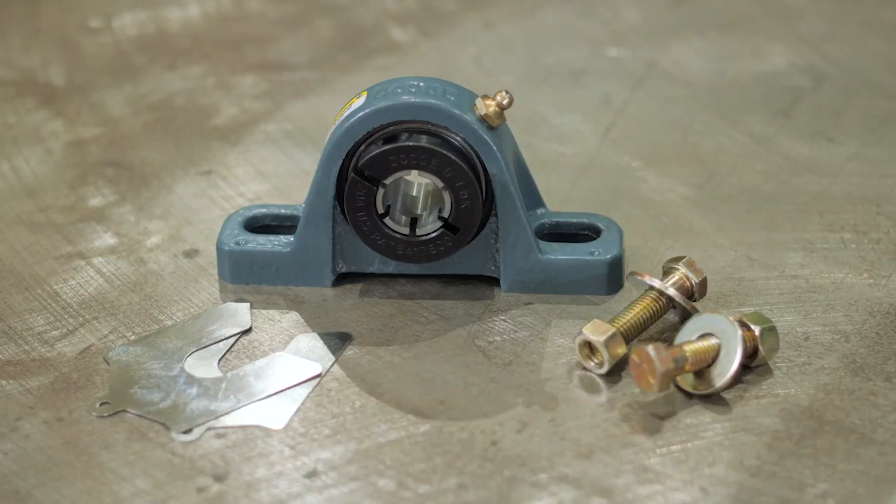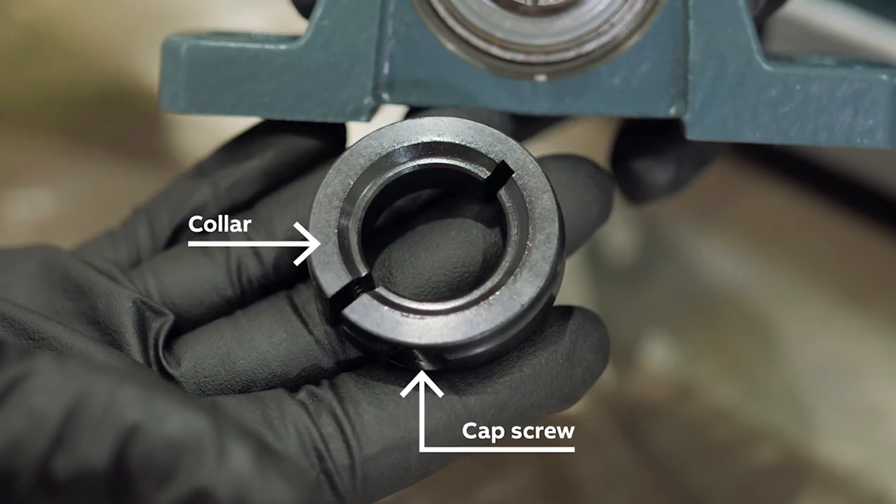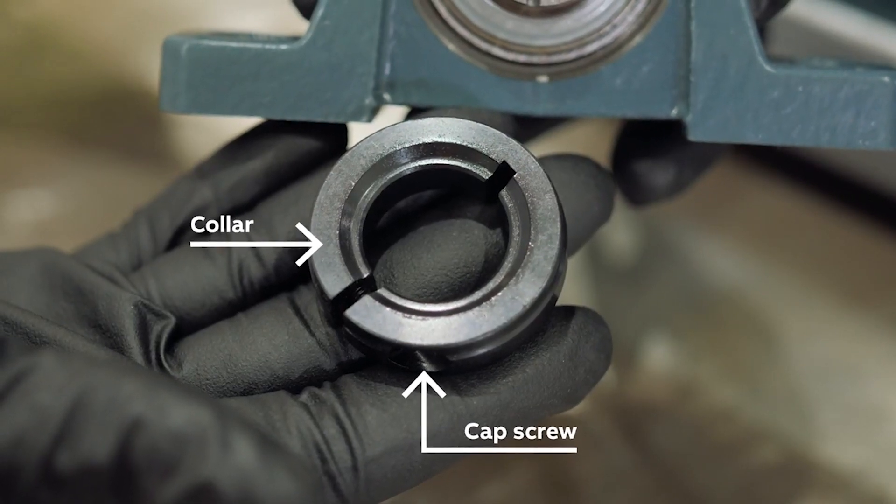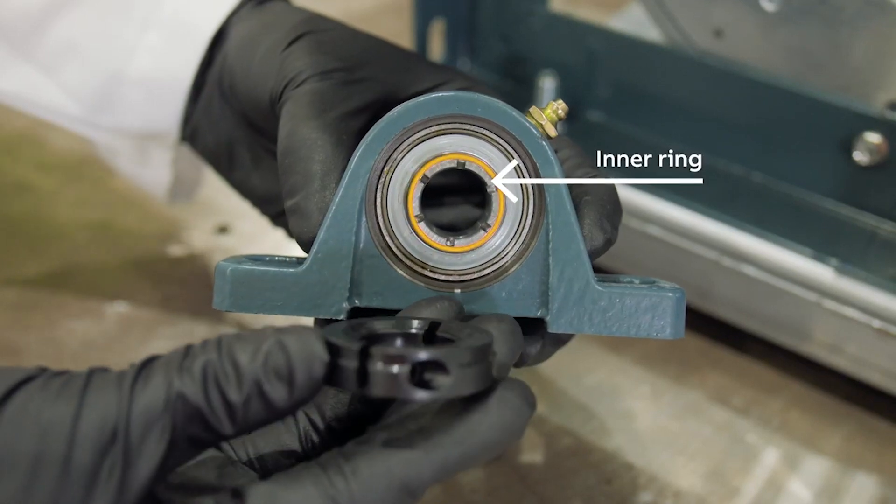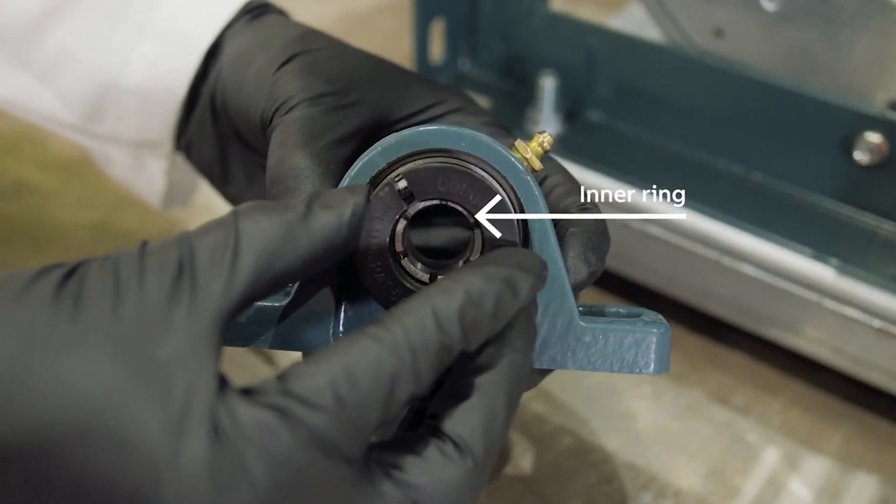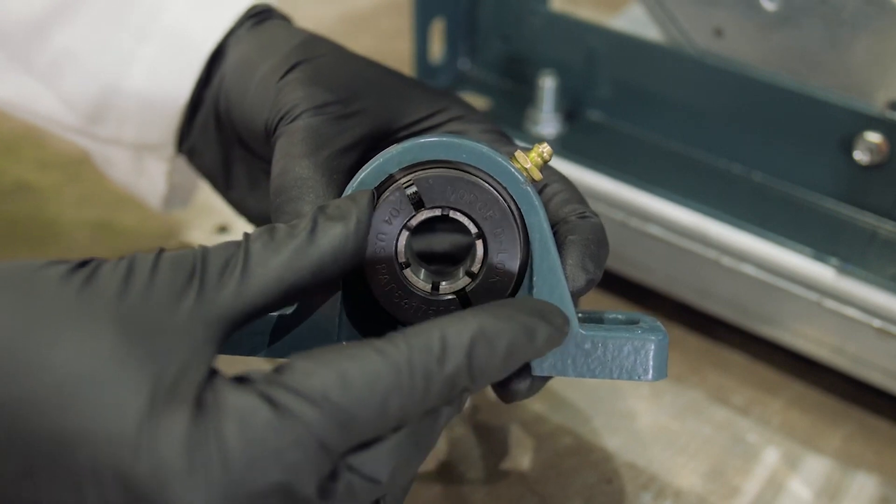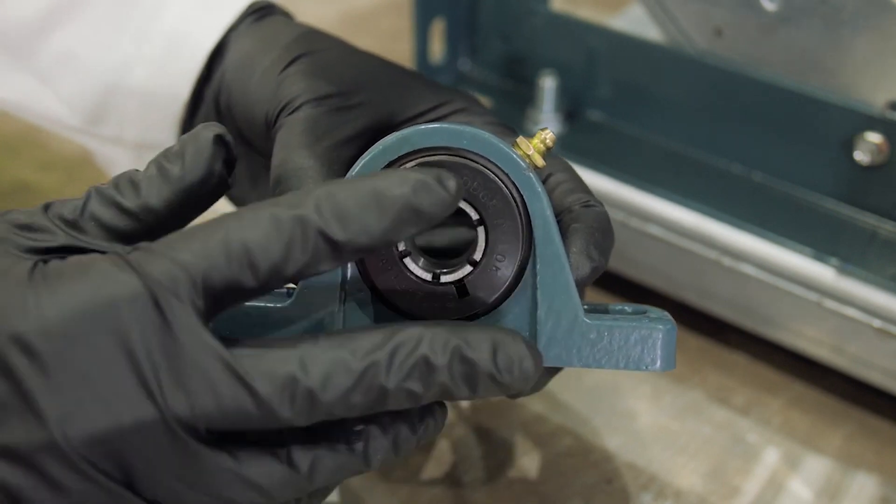Dodge D-Lock bearings are attached to the shaft by a unique locking mechanism featuring a collar that sits on a specially machined inner ring. As a single cap screw is tightened, the collar compresses the inner ring and attaches the bearing to the shaft. Keep the collar square against the shoulder of the inner ring throughout the installation process.